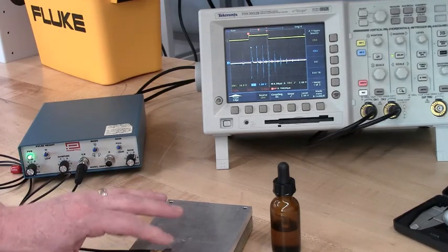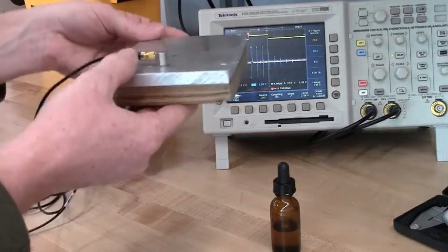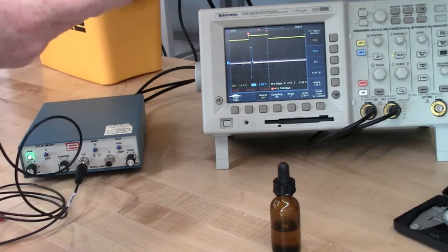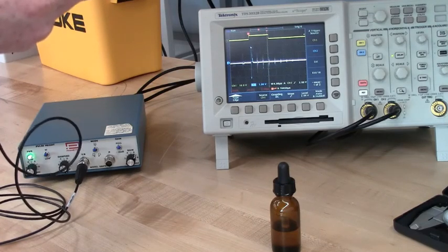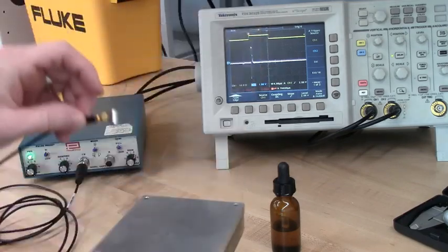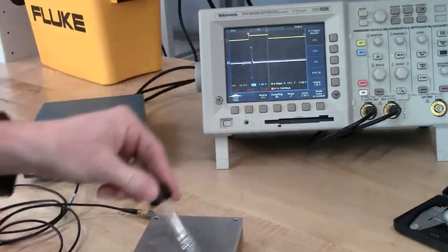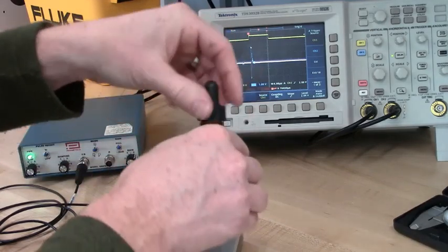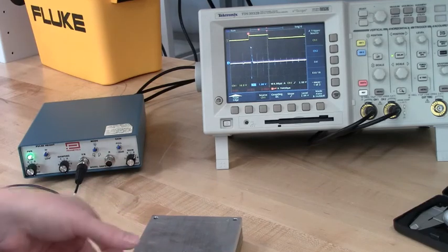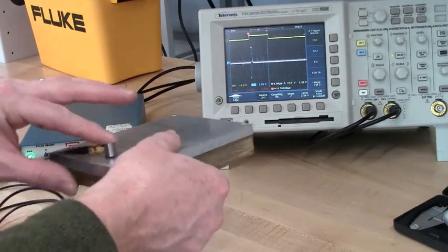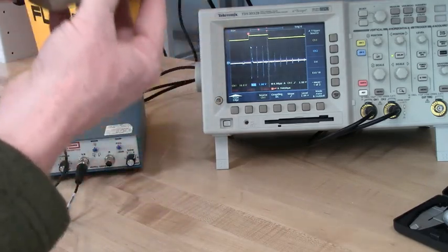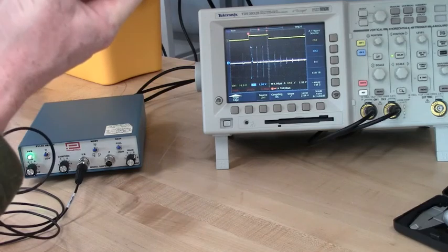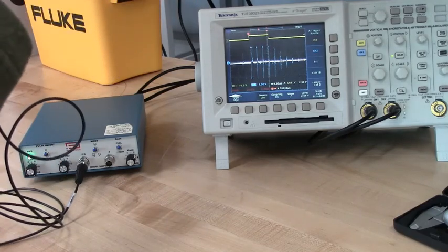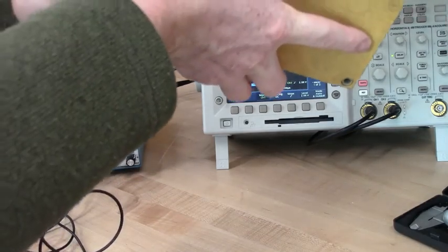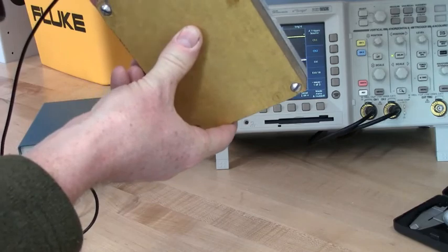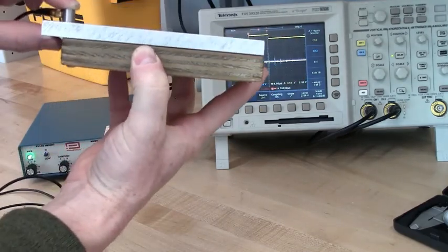Look here, I have the sample. I have some glycerin here. Maybe I could use a little more glycerin. We don't want to put a lot on, but we want to make sure we get a good signal. So you can spread that around a little bit. So that looks good. And see, right now we are over a place of known thickness, right? There's nothing machined into the backside of that there. So we can measure that thickness.